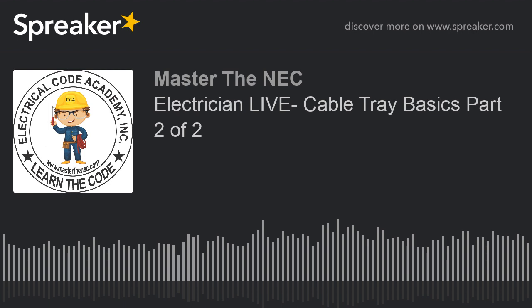when I'm doing that, again, we're talking also about making sure they're lashed down. For example, single conductors are lashed down when they're in the group to prevent excessive movement due to fault current, the magnetic forces that can take place. Okay? Unless, of course, single conductors are cabled together, such as in a triplex, then they're already connected together and they're acting as one. Okay?